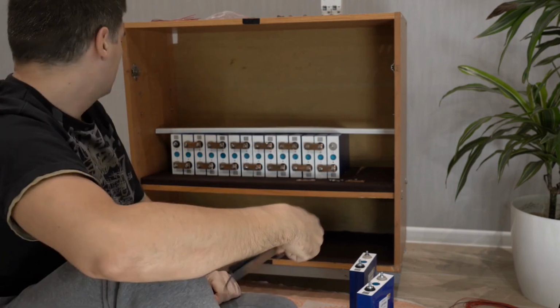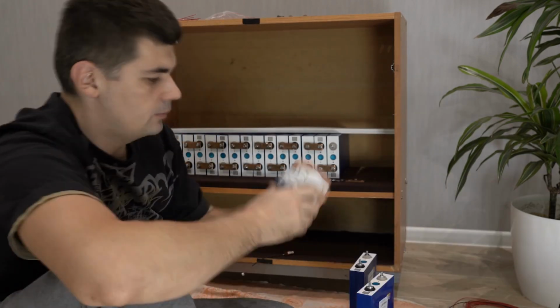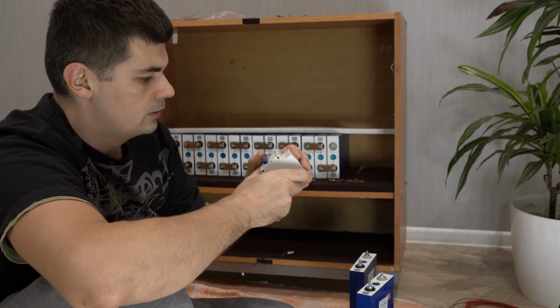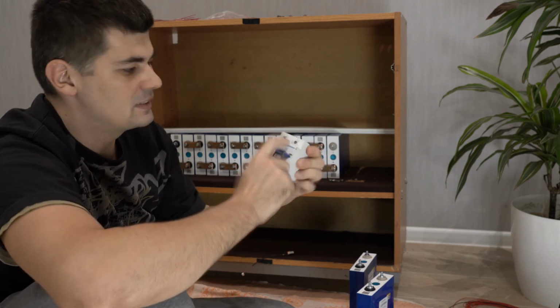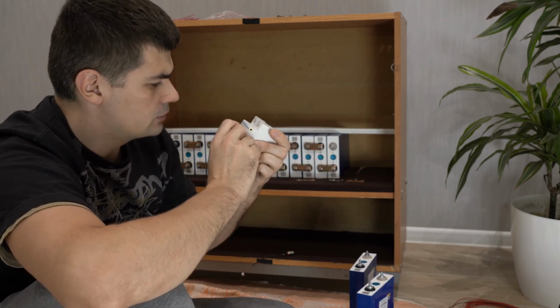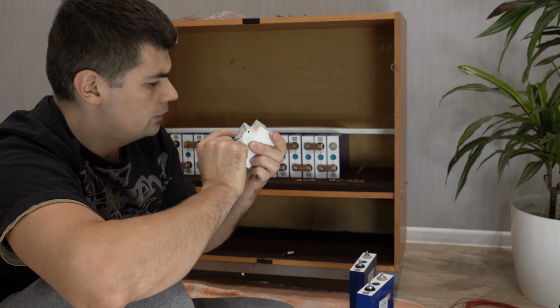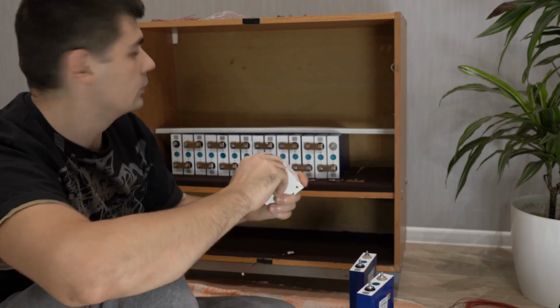We'll also need a circuit breaker. I'll install a 100 amp circuit breaker, I don't have a larger one. It's a DC circuit breaker, rated up to 800 volts and 100 amps. Well, I'll try it, 100 amps should be enough.